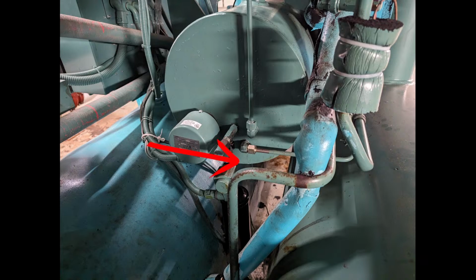So this is the hot gas line coming in, and here's our eductor line. There's a valve down here off the side of the evaporator. This particular one is a falling film style evaporator, so it sits a little lower down on the evaporator itself. Either way, this is our eductor filter, and this is the solenoid valve that controls the eductor system. When it needs to go into a recovery state on the oil side, it energizes this valve, opens this assembly, and allows hot gas to push through the eductor assembly to start siphoning that oil-laden refrigerant off the top of the liquid level in the evaporator.